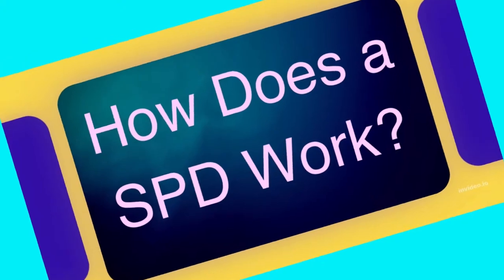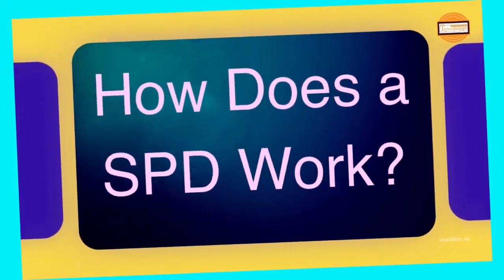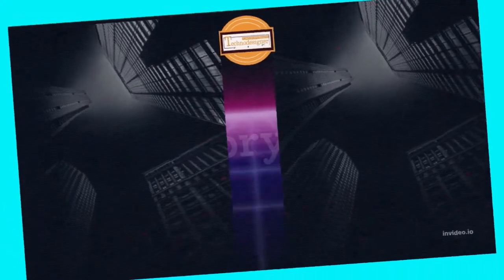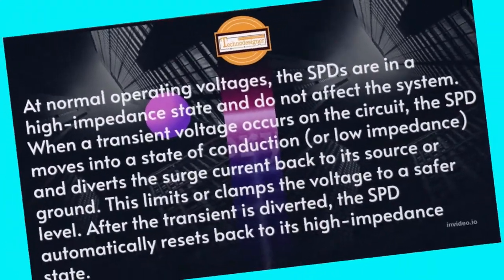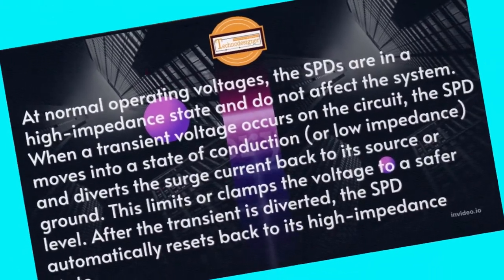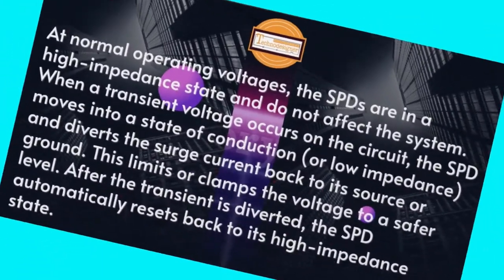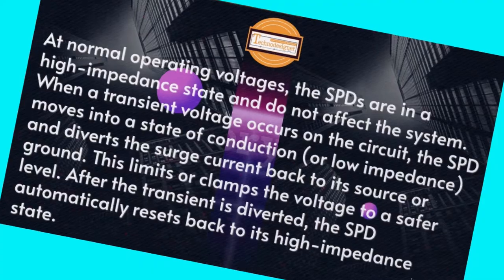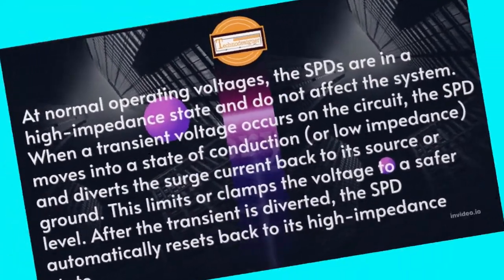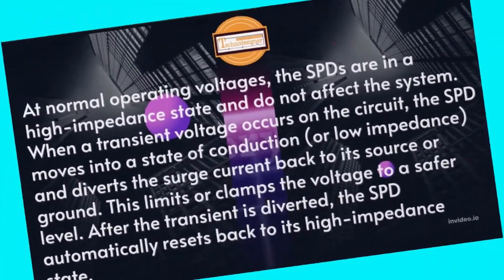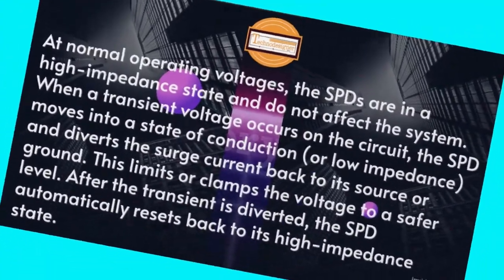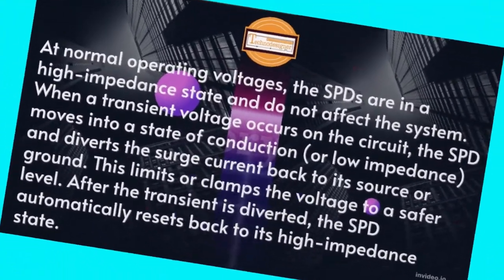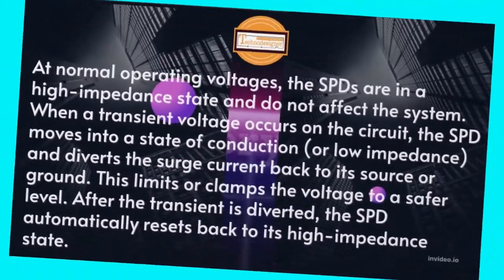How does SPD work? At normal operating voltages, the SPDs are in a high impedance state and do not affect the system. When a transient voltage occurs on the circuit, the SPD moves into a state of conduction, or low impedance, and diverts the surge current back to its source or ground.